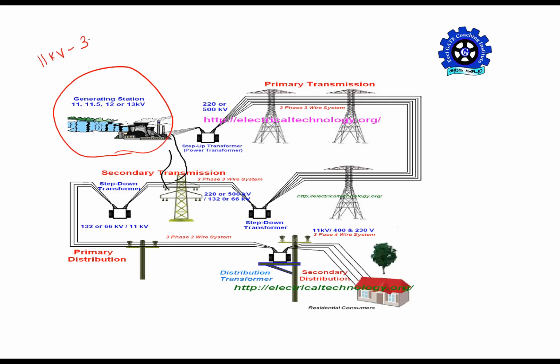We cannot go for high voltage generation because of alternator issues — the alternator size would become exorbitantly big. The stator slots and the amount of insulation needed between conductor slots would increase, making the stator size very large. So we cannot handle such big stators.